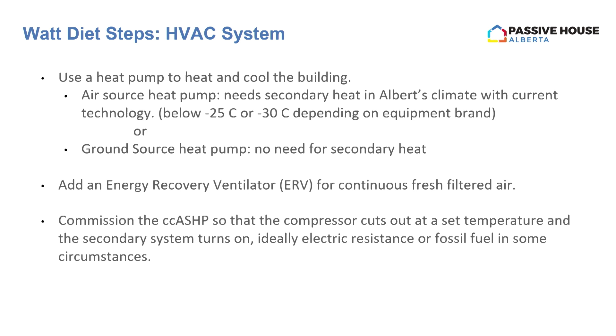And then the other thing that we've learned from both this study and a new study we're doing right now is that when we're commissioning that cold climate air source heat pump and the secondary heating system, we want to make sure that there's an actual control so that we use one or the other, not both. Because at some point the air source heat pump is no longer efficient and we should switch to the secondary. We don't want both to be running because then we can increase the peak load. We have 2 large systems running as opposed to just one or the other. And that secondary heating system, we prefer to be electric, but in some cases, fossil fuel is still a good option.